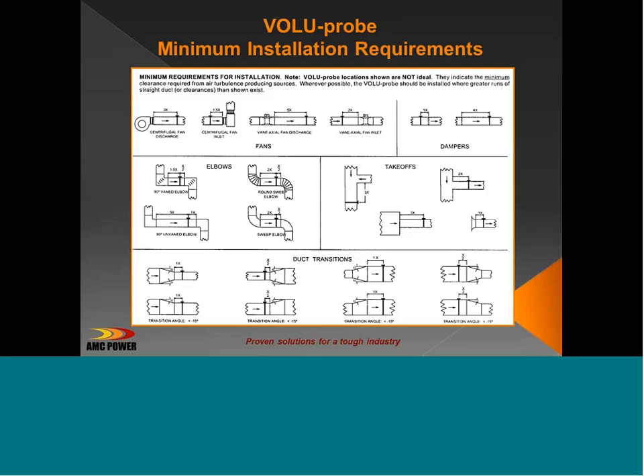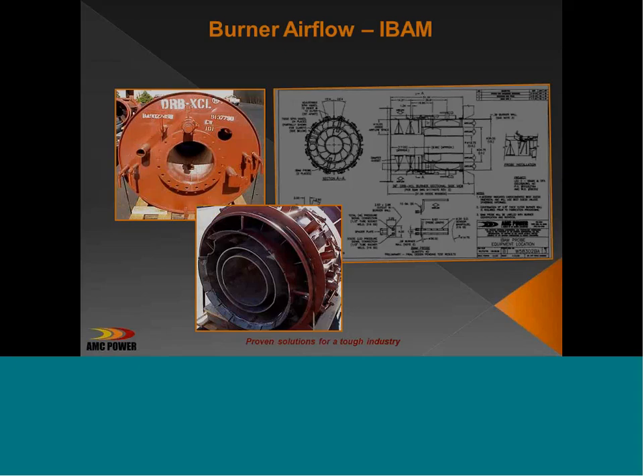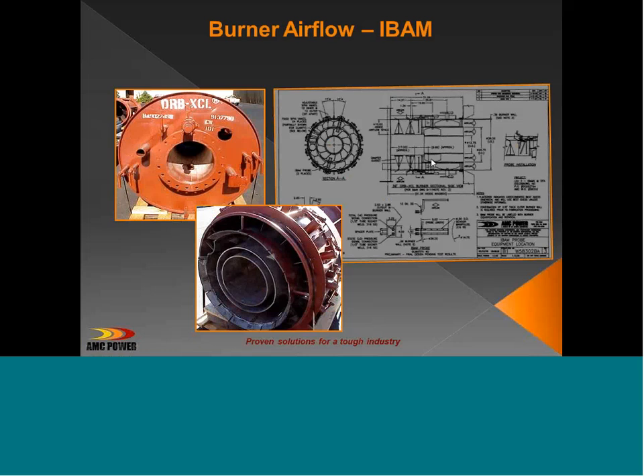So the challenge, again, for a burner is how do we measure airflow in a burner when there's not even one duct diameter? This is a schematic of a burner, and where we might put our pitot tubes in this burner. Not only is it a short duct run, we've also got swirlers in there. We're trying to create swirl, which adversely affects pitot tube measurement. So the challenge was to develop a flow measurement.